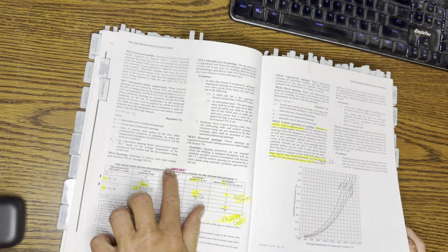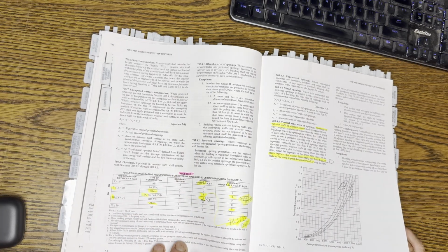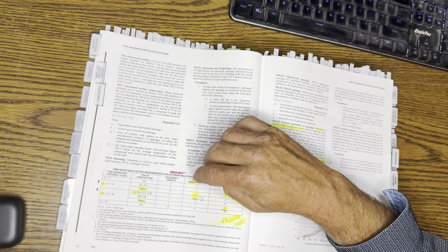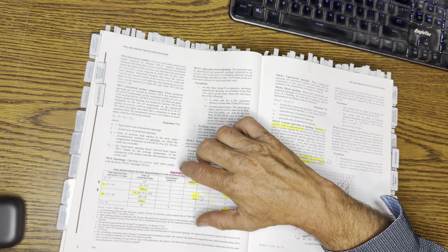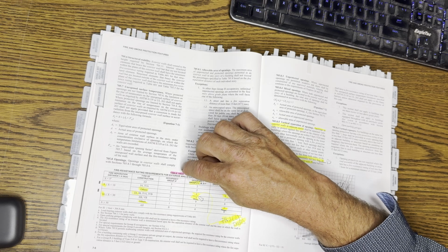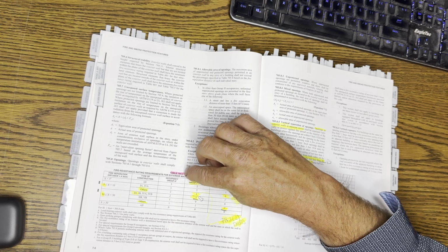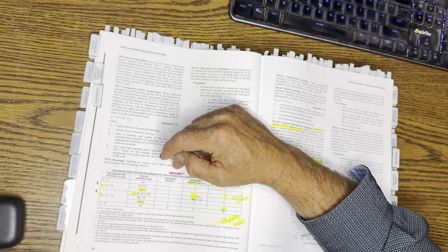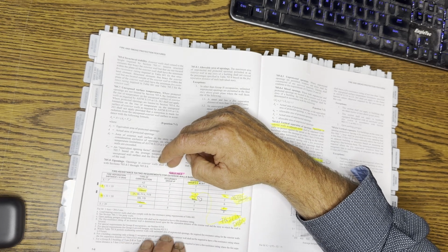This is a really important section. Let me explain how this works. 705.5 changed from the 2018 to the 2021 version. In 2018, it used to be Table 602 in Chapter 6. They moved this to Chapter 7. But there's a lot of confusion on this chapter, and it's really important to understand how to read this.